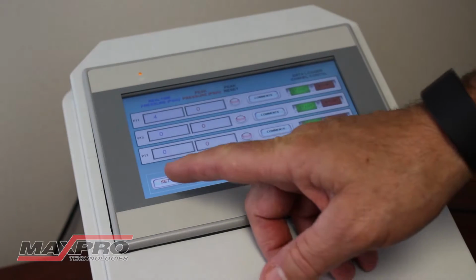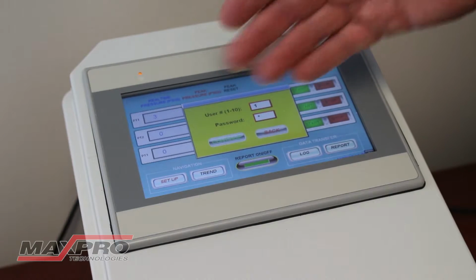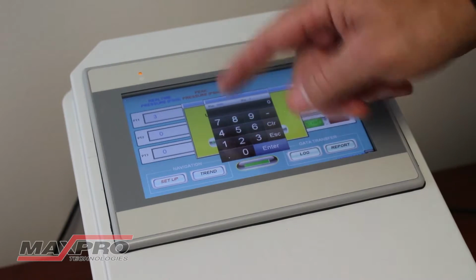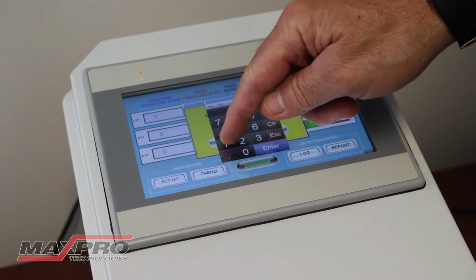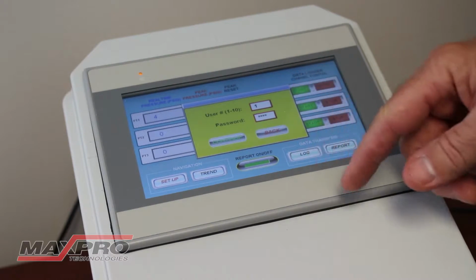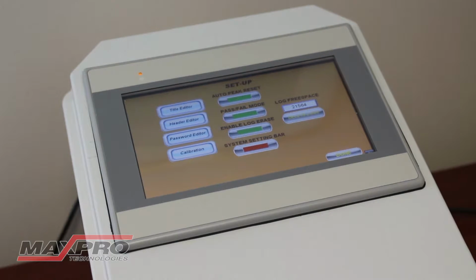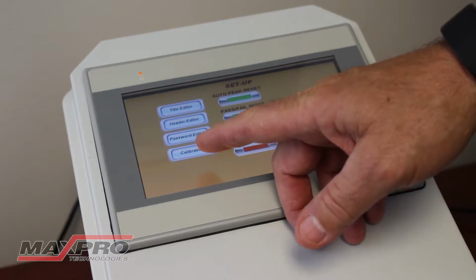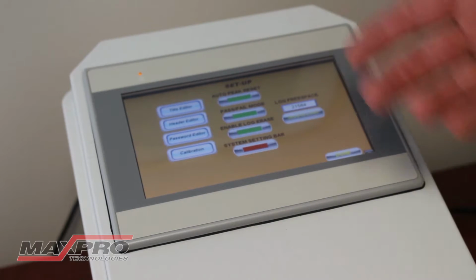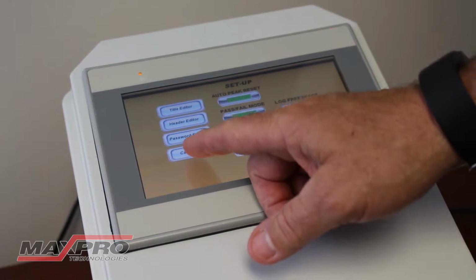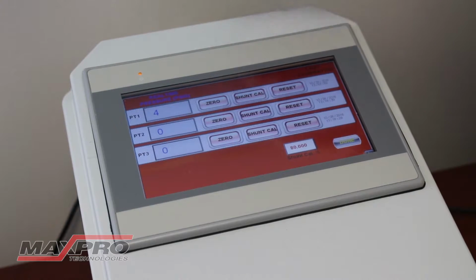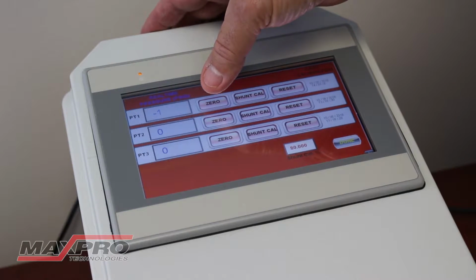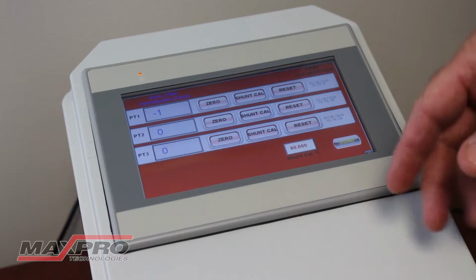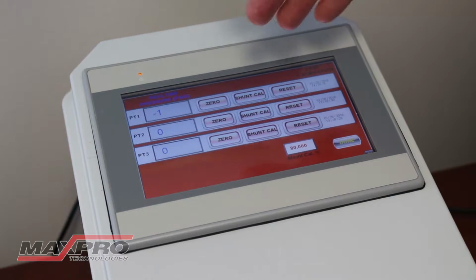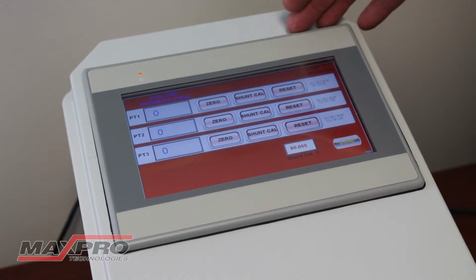So the first thing we'll do is we'll go to the setup screen. The unit is password protected here. When it comes from the factory, it's 4 ones, and then hit enter, and you can get into the setup screen. That's something you can also change by going to the password editor if you want to put your own password in there. So one of the things you can do from this screen is go to the calibration, where you can zero each one of the pressure transducers after you've got them hooked up, and then there's a shunt calibration function that you run as soon as you hook the unit up to a new transducer to calibrate the transducer to the logger.